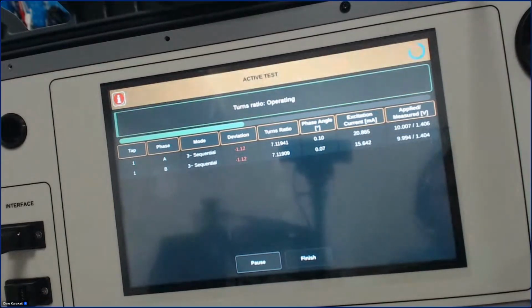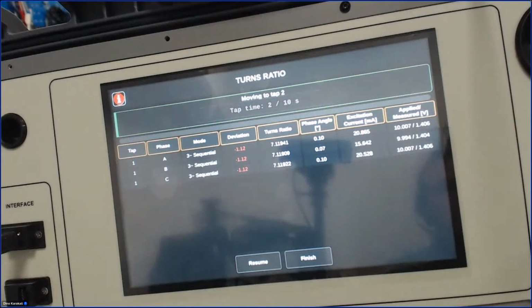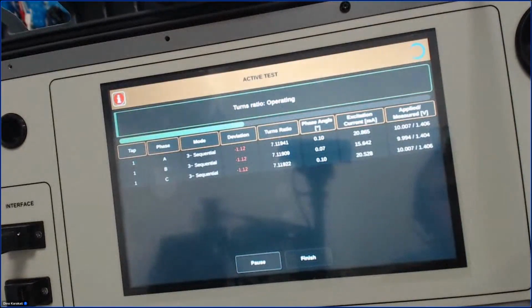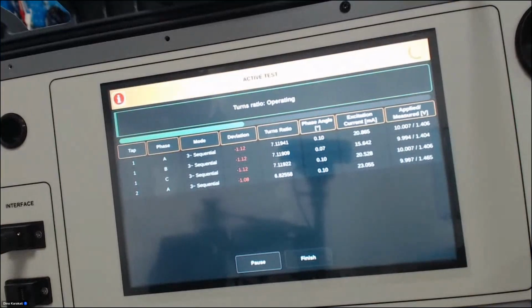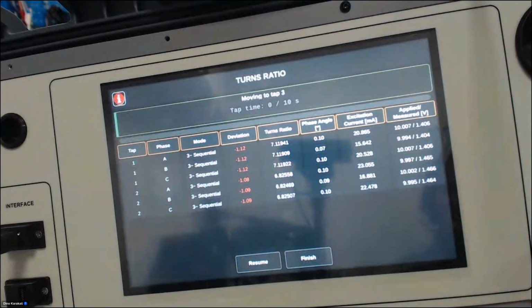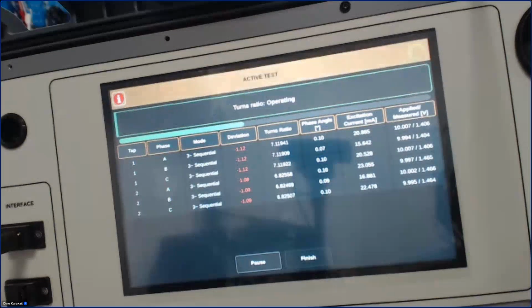Turn ratio result, phase angle results, and excitation current are shown. You can see that this goes pretty quick with the turn ratio test. We selected only sequential test to be performed. The device changed to tap position number 2, and now we'll perform the turn ratio measurement for tap position number 2. And tap position number 2 is done.